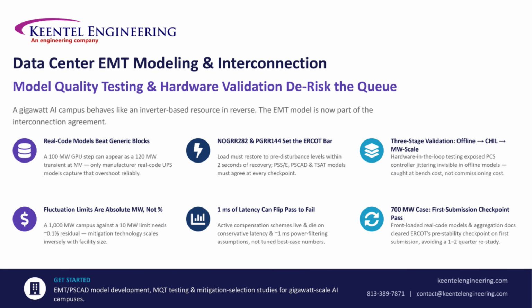And precision matters enormously here. 1 millisecond of extra latency can flip a compliant design to non-compliant, which is why fluctuation limits are absolute megawatt numbers, not percentages, and mitigation technology has to scale with facility size. We've seen this discipline pay off directly. A 700 megawatt AI campus that front-loaded real code models and aggregation documentation cleared ERCOT's toughest checkpoint on first submission, avoiding a 1 to 2 quarter restudy.